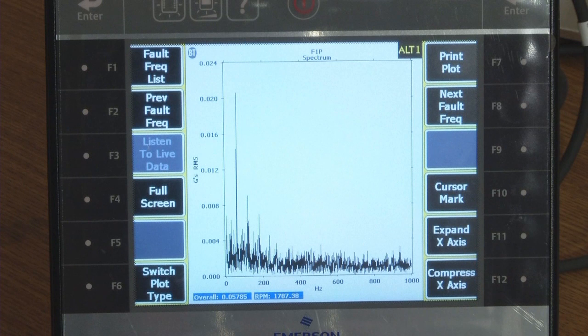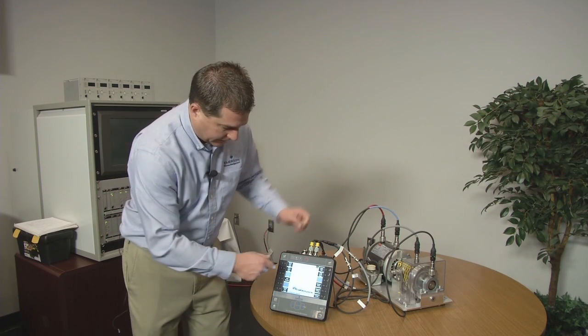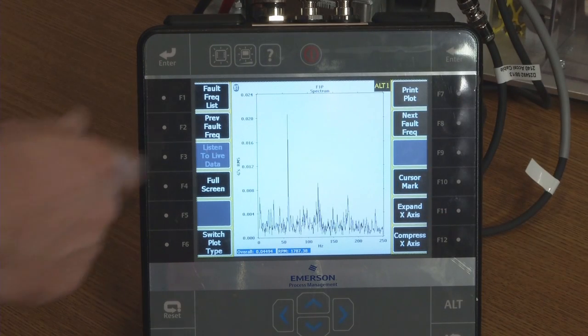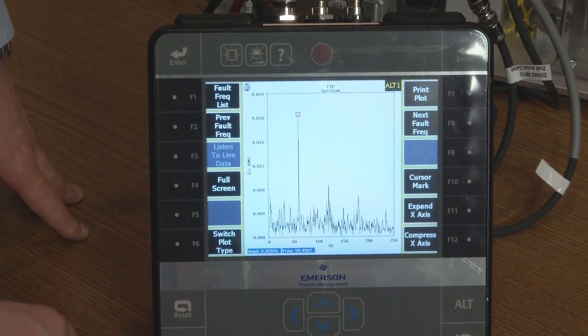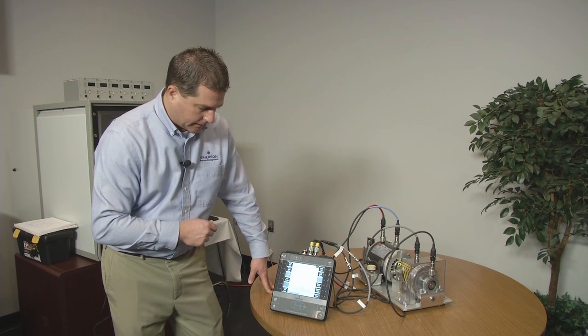And so you can see it come up here and I've got this really large peak down here in the lower frequency zone. And I'm assuming that's probably my two times turning speed peak. I'm going to expand my X axis by pressing F11 here so I can see that peak a little better. I'm going to touch the screen and I'm going to mark this peak.